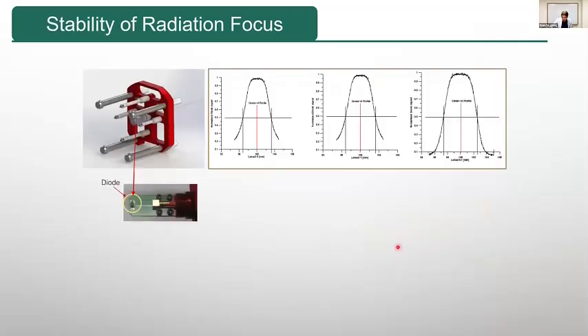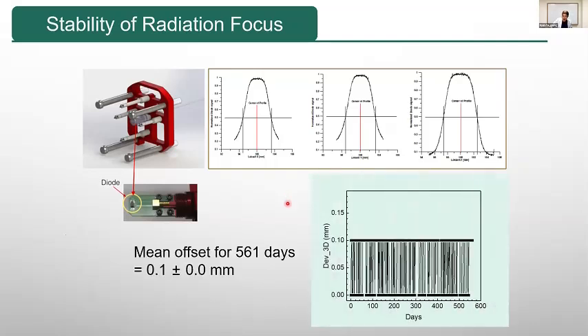And there is another tool, a simpler one, to check the mechanical accuracy. There is a diode detector at the center of this tool, and we check the radiation dose distribution with this diode detector every working day. The center coordinates in X, Y, and Z were measured automatically, and it tells how much error was found. Over the long period, the mean offset was only 0.1 millimeters. So we can say it is a very stable machine.